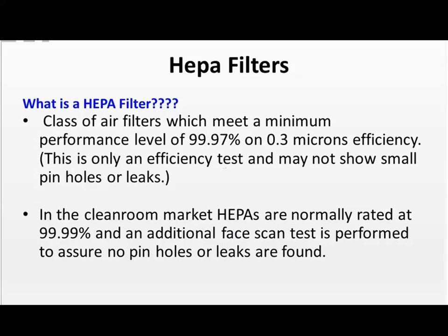And I just mentioned that we have HEPA filters in our rooms, and these HEPA filters are what are filtering out our air and filtering out the particles. The class of the air filters, which is going to meet a minimum performance level of 99.97% on 0.3 microns efficiency.